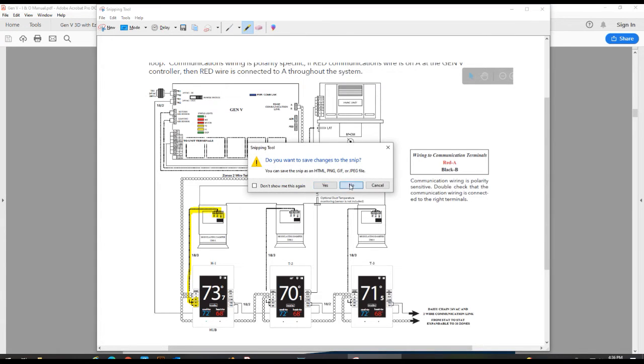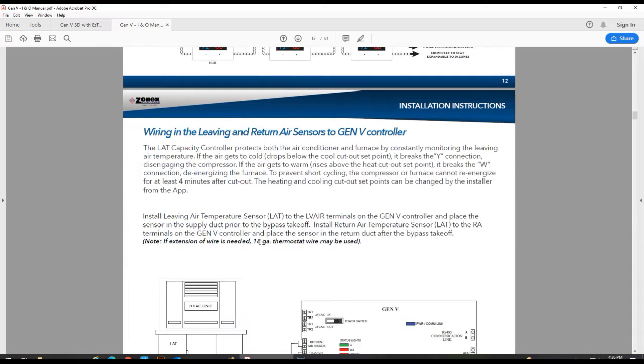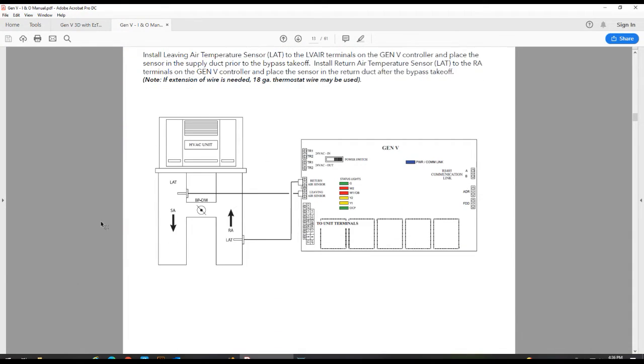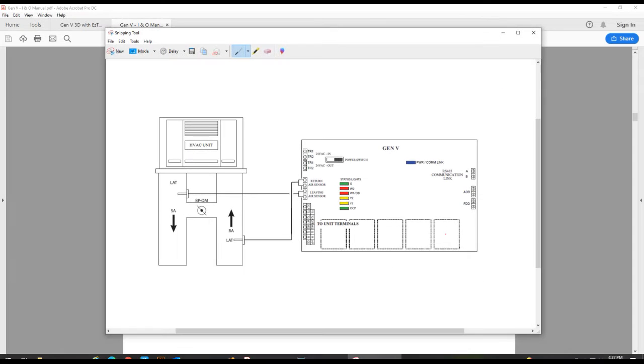Alright, so moving on. The Gen V controller, as mentioned before, has several sensors that are utilized. These sensors are important to the operation of the Gen V controller. So we want to go ahead and make sure we land them in the appropriate spots. You have a leaving air sensor. This should be installed in the supply trunk, roughly 18 to 24 inches downstream of your coil, but before the bypass. This sensor is utilized for capacity control as well as staging.